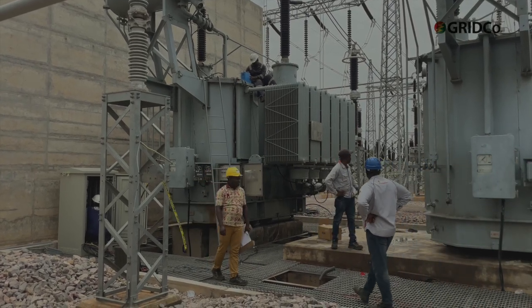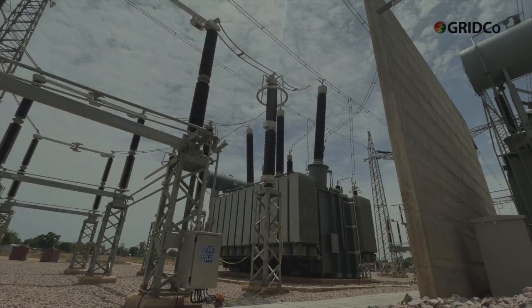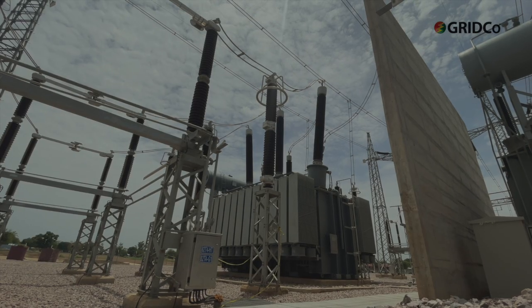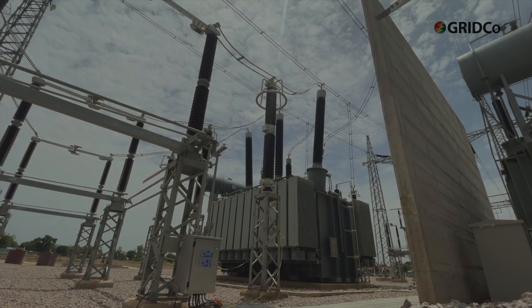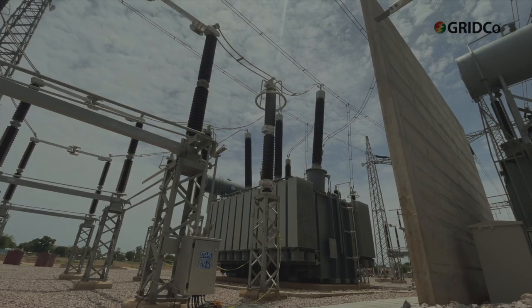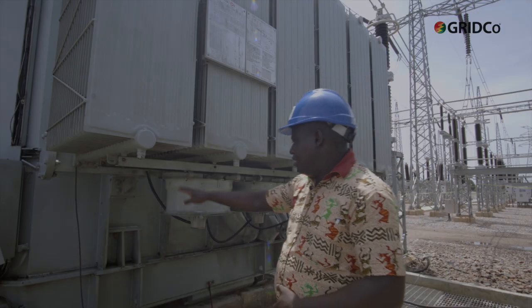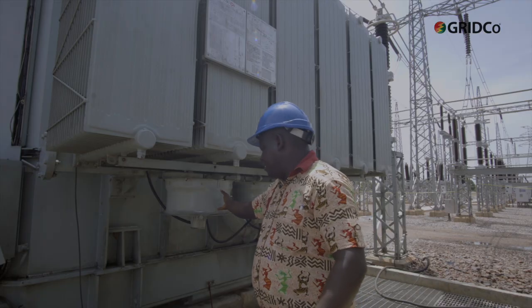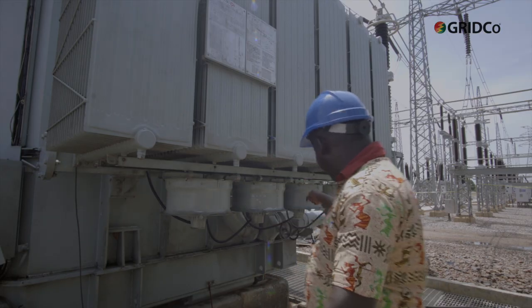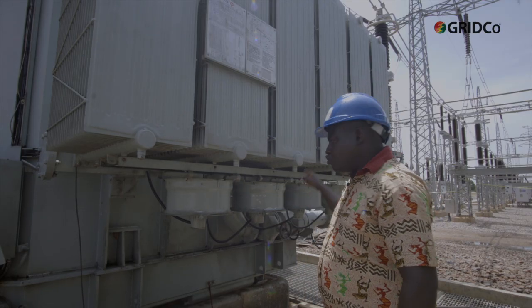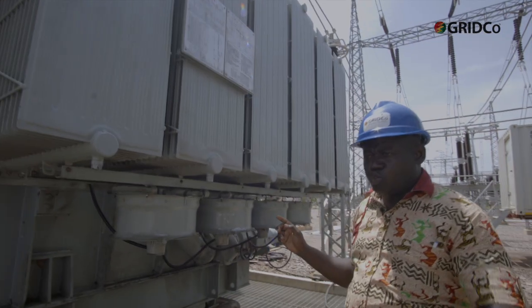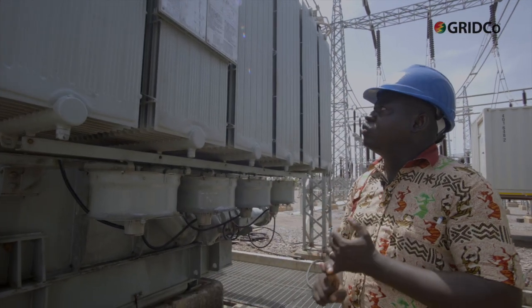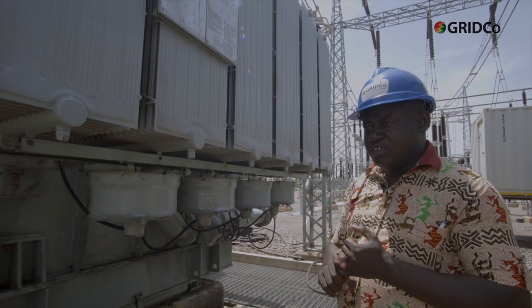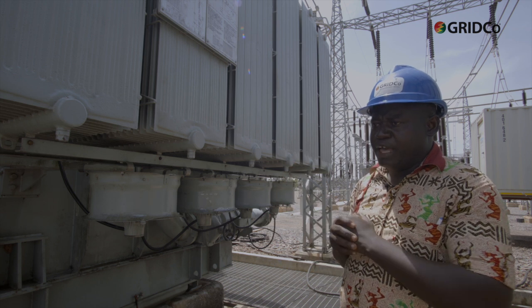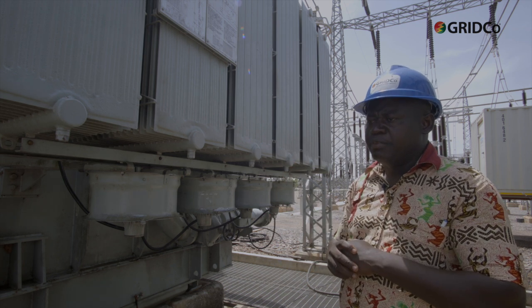But the one we have here is 3. Now, for you to get to the full load, which is the 200/3, that one is oil forced, air forced. What it means is that the fan is there, you are forcing the cooling, and then there's also a pump, which is also forcing the oil to do the cooling. So you have oil forced, air forced. That is the type of cooling system that we have here.